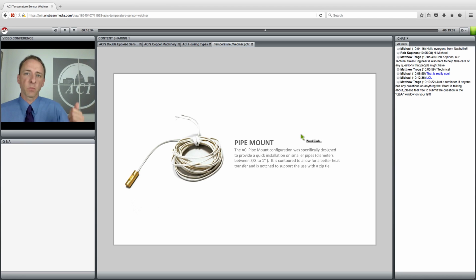This, I mentioned briefly, is a sensor that can be strapped onto a pipe for smaller pipes than the 2 to 5 inch. And this is our newest of all of our configurations, and we call it simply the pipe mount. It's a short brass, 1 inch brass probe that is crescent shaped, so it fits nice and snug up against a smaller pipe, anywhere from a 1/2 inch up to 1.5 inch diameter pipes. And we ship it with wire ties that fit right into that little notch you see there, so it gives a nice, tight, secure connection to the pipe for those real small pipes that a standard strap-on type sensor won't fit.